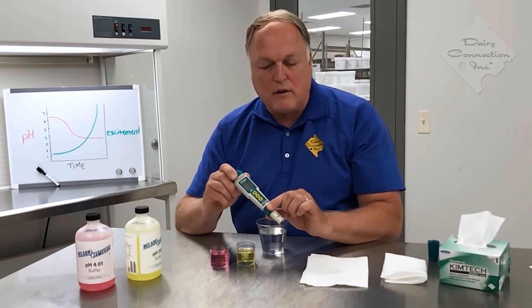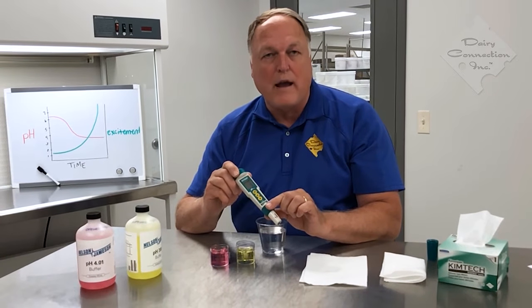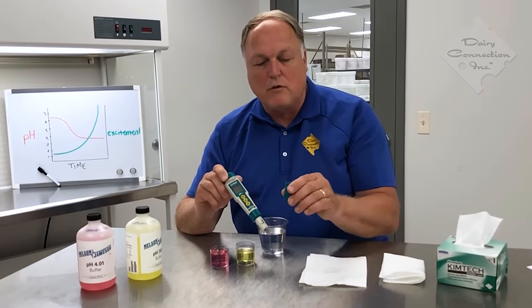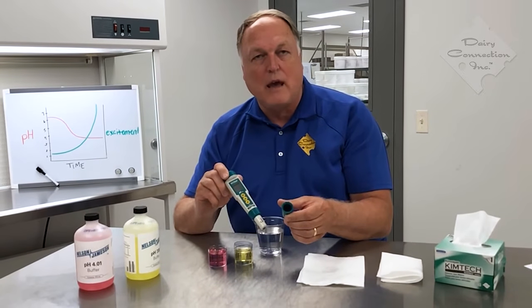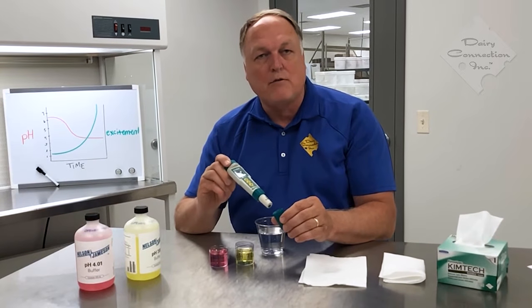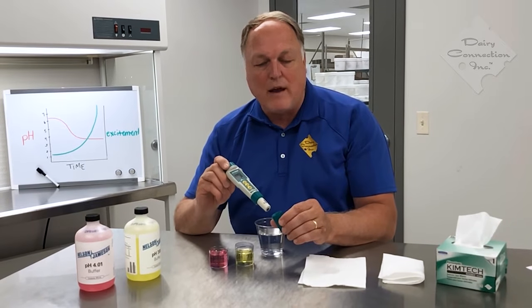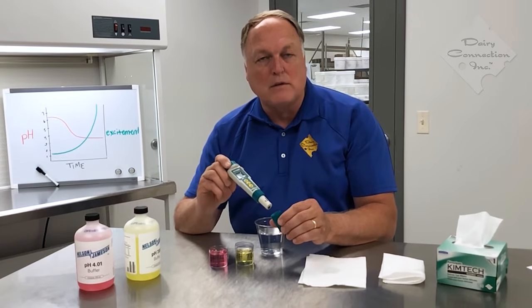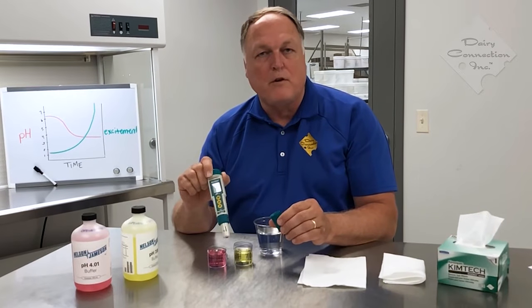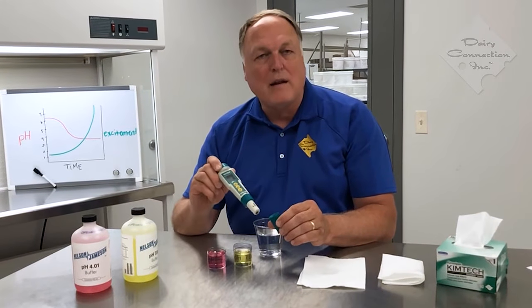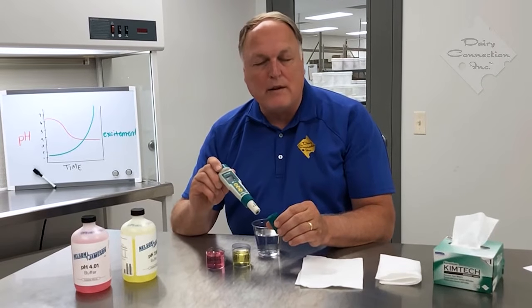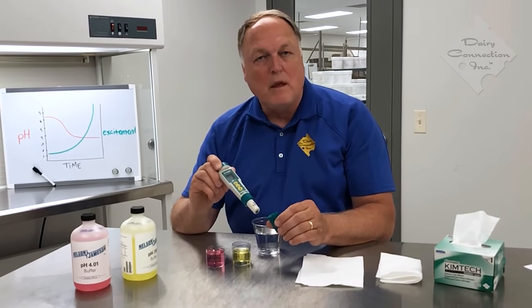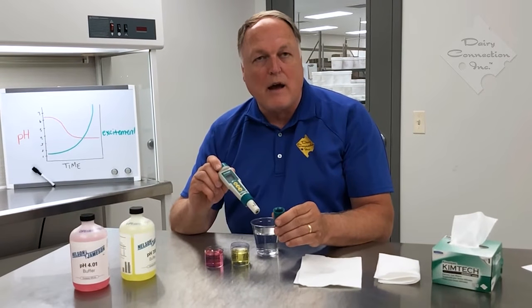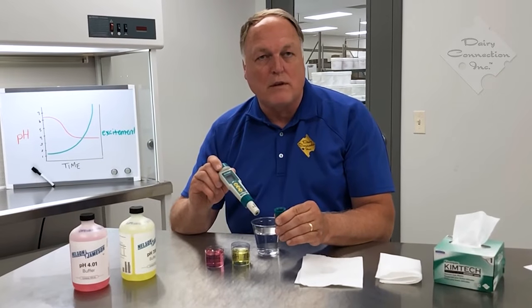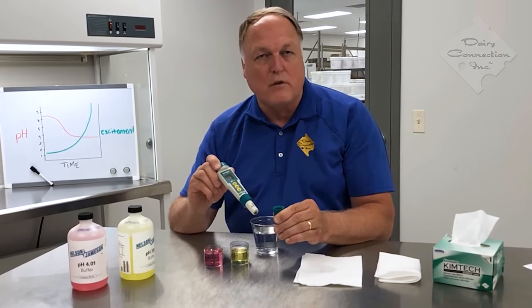Other things that can cause issues with the electrode is if it were to dry out. Our recommendation is to store it in a cap. There's a sponge in the cap with liquid. Always keep the electrode tip wet. If it does dry out, it may take up to 8 hours of soaking in a 4 buffer to rehydrate and reactivate the electrode. So that's one thing to check on when you get a new electrode. Is it wet or is it dry? And my recommendation is to soak it for at least 4 to 8 hours before using it the first time.